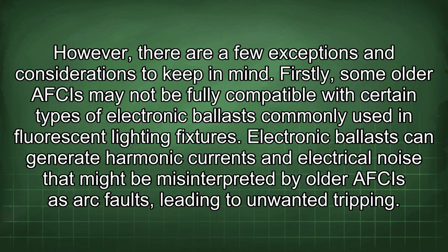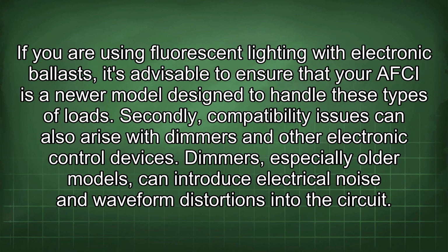Firstly, some older AFCIs may not be fully compatible with certain types of electronic ballasts commonly used in fluorescent lighting fixtures. Electronic ballasts can generate harmonic currents and electrical noise that might be misinterpreted by older AFCIs as arc faults, leading to unwanted tripping. If you are using fluorescent lighting with electronic ballasts, it's advisable to ensure that your AFCI is a newer model designed to handle these types of loads.